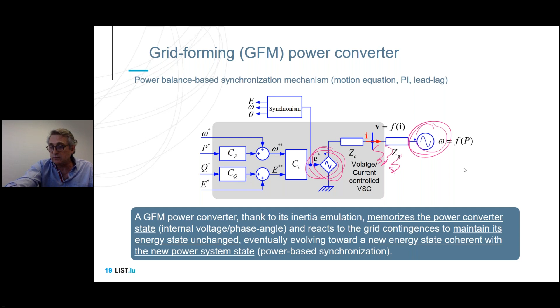With respect to the instantaneous dynamics of the grid, the internal state of the converter will remain unchanged in case of any disturbance, and automatically the converter will react to such a disturbance, as in the case of a synchronous generator, progressively moving to a new coherent operation state after the disturbance is removed. This is a simple representation of what we consider a grid forming converter to be.